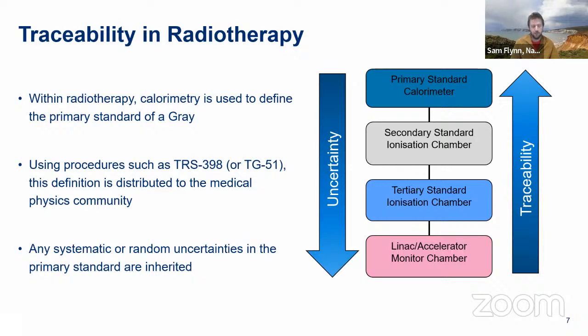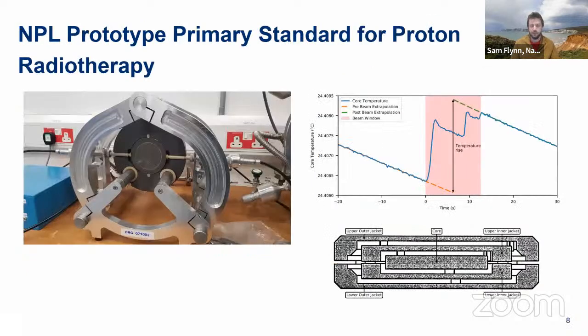In the National Physical Laboratory, we use graphite calorimeters for our primary standard measurements. This is a photo of our graphite primary standard calorimeter. Calorimeters are really simple devices. I'll show you the equation shortly, but energy is deposited within the sensitive volume, which is the core. It causes a small temperature rise, and if you can measure that temperature rise, you can work out the dose that was delivered to it. These devices are typically operated in what we call quasi-adiabatic mode, in which the temperature is allowed to drift, but in a controlled manner. Then we do a fitting technique between before and after the beam to work out the midpoint and extrapolate the radiation-induced temperature rise.